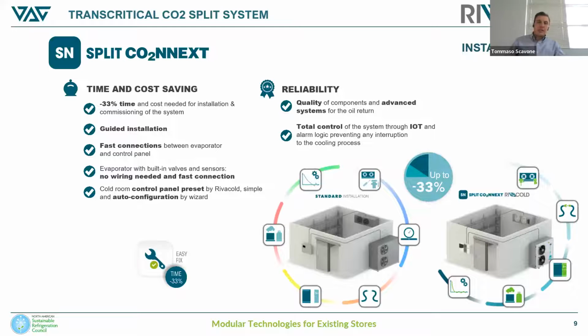From the installer side instead, we have up to 33% time and cost saving compared to a standard installation, thanks to several factors. First of all, the fast connections between evaporator, control panel, and condensing unit, those cable kits that I mentioned previously, but also the thermostatic valve and the probes that are already fitted to the evaporator, saving both the sizing and the brazing time on the TXV, and the wiring process for the probe. Plus the cold room control panel comes already preset from the factory. We are practically reducing the installation time only to the copper piping and the equipment placement.